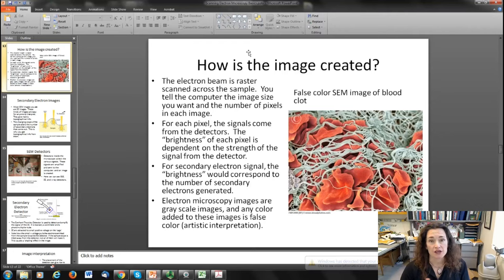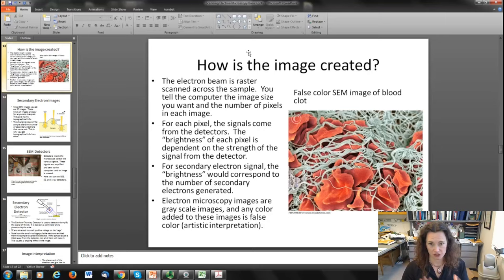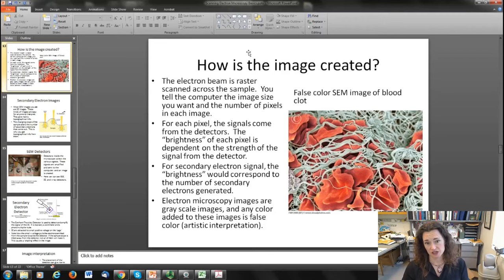The image is created by scanning the electron beam across the sample and monitoring what signals come out at each pixel. You tell the computer the image size you want — how big the scan should be in micrometers or nanometers — and also what resolution you want, meaning the number of pixels. For each pixel, signals come from the detectors. The brightness of each pixel is dependent on the strength of the signal from the detector. For a secondary electron signal, brightness corresponds to the number of secondary electrons generated — brighter for more electrons and darker for fewer.